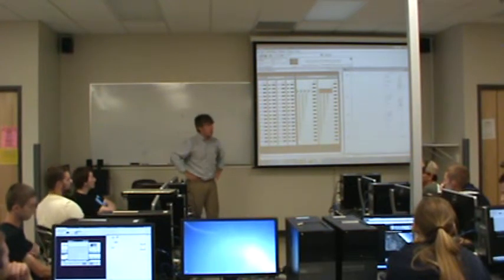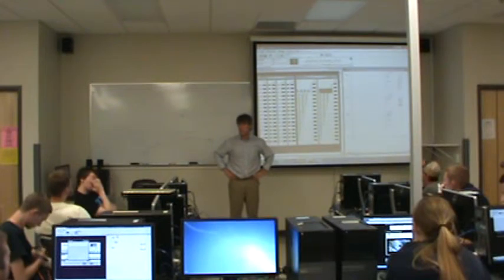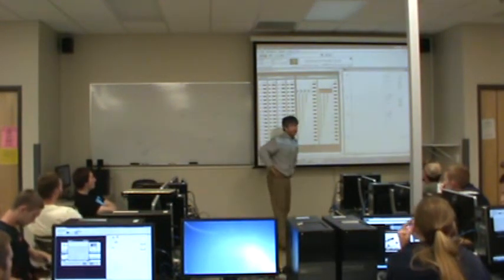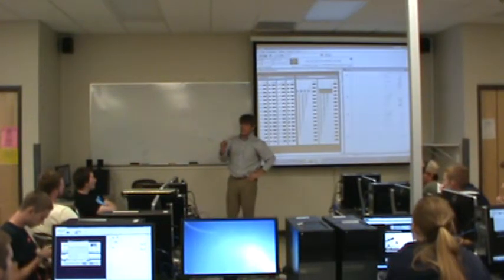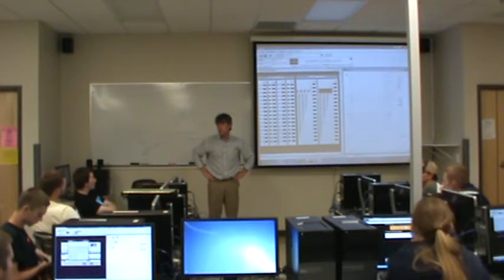And depending on the PLC, it may just truncate it. It may just throw away the extra numbers, and then you get a result that doesn't make any sense. Another thing to know with the divide: when you divide 2 numbers, it's very easy to get things after the decimal place, right? It's easy to get fractions of a number, okay?